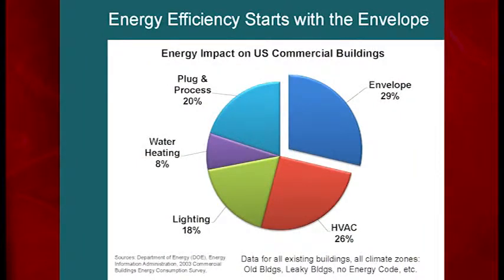Do buildings use a lot of energy? When I ask people what uses the most energy inside a building, they invariably say air conditioning. As a mechanical engineer I don't like that response. The reason you say that is because the envelope and fenestration — you don't plug those things in and you don't see how much electricity they're causing to be used. There's nothing about my system putting heat into the space; it's the electrical engineers, the people in the space, and the architects. If you design the perfect envelope and an amazing lighting system, you wouldn't need my system to take the heat out of the building.